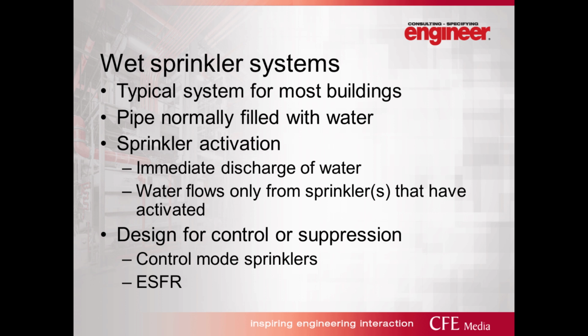Upon a sprinkler activation, the discharge of water is immediate because it is already sitting in the pipe where the sprinkler is, and water flows only from sprinklers that have activated.